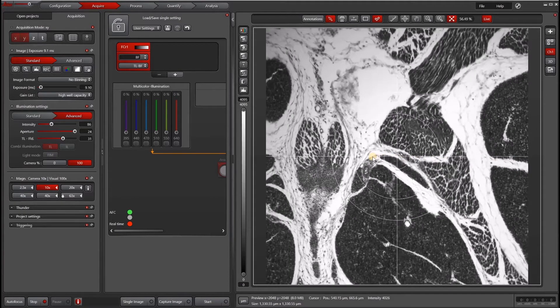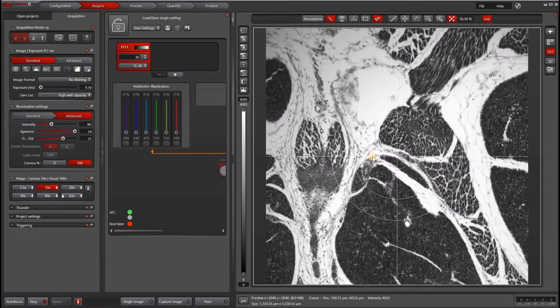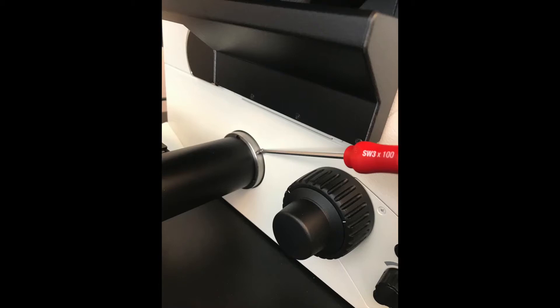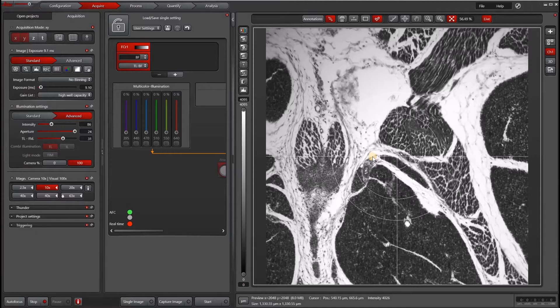The next thing we want to do is loosen the C-mount from the base of the microscope. I took a picture of that from a DMI-8 microscope stand. If you're using a DM-6, an upright microscope, that might look a little different. But essentially you definitely want to rotate the C-mount from the base of the microscope and not from the camera. If you rotate the camera, you may unscrew the camera from the C-mount and this is not a good thing. It makes everything unstable. So make sure you use a 3mm Allen wrench to unscrew the C-mount.